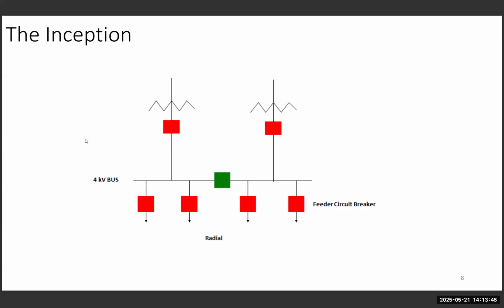On a very high level, under normal conditions, these represent two different substations connected together. Under normal condition, which is like 99% of the time, the two stations are completely independent. But if you lose one of the transformers, the other side will kick in after a momentary interruption or a long interruption. That's known as an N-1 design - you lost a component, N is normal, so it's normal minus one, meaning it's not a normal design anymore.